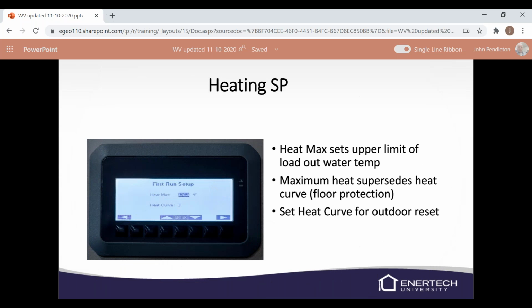Next, it'll ask what your max heating set point is. So if you set it at 135, but you need floor protection, it will still look for your floor protection. The 135 is the max temperature it ever wants to see out of that unit. So that's the max temperature it would send to the air handler. If it sees a radiant floor call, then you can set your floor max temperature as well in a later screen. You can set your heat curve here as well.